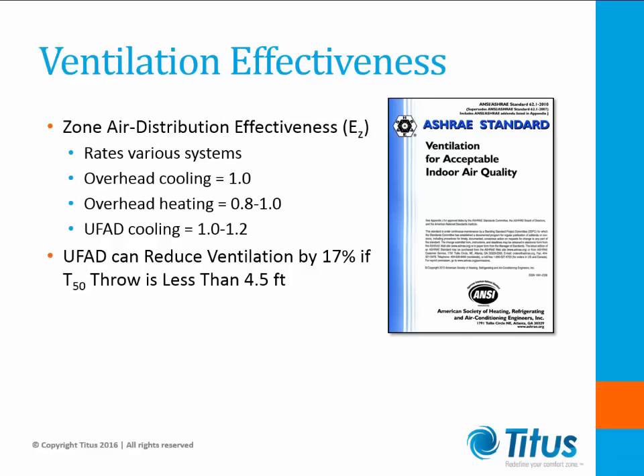This means that if the minimum ventilation requirement for an office environment is 5 CFM per person, the system must deliver at least 5 CFM per person. If the same space were supplied from a floor plenum using low velocity diffusers with a vertical throw to 50 feet per minute equal to or less than 4.5 feet, the EZ value would be 1.2. Anytime the EZ value is greater than 1, the amount of ventilation air is reduced. For the low velocity floor supply, the ventilation per person could be reduced by 17% because EZ equals 1.2. I should point out that this reduction in ventilation may not comply with local code requirements, so check first with local officials.